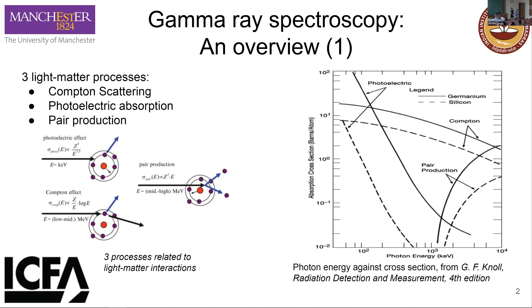We'll use the detector to calculate relative characteristics, with the detector's resolution and efficiency. And as you can see, there's the actual crystal you can determine. So just to make a comparison, sorry for all the text: scintillators emit visible light through the previously mentioned processes, and impurities were added to ensure that the emitted light is within the visible or detectable region of the photon spectrum, and is then consequently detected with a PMT or other devices.